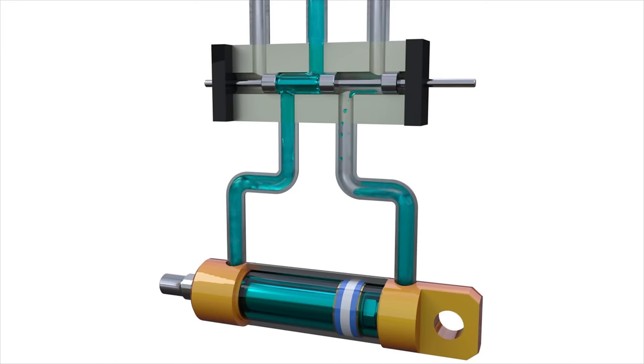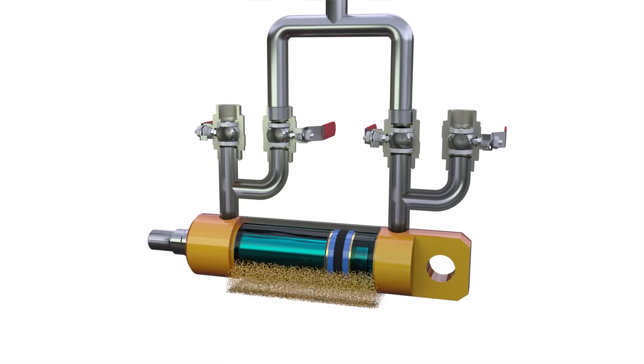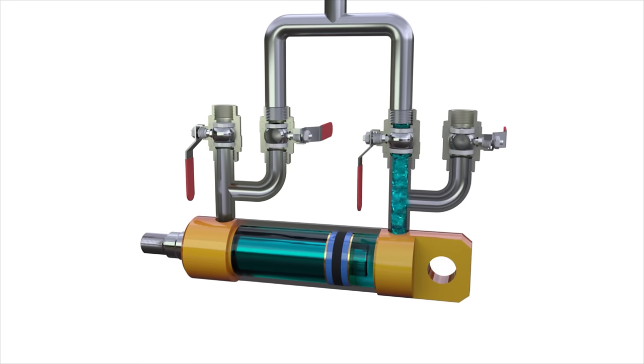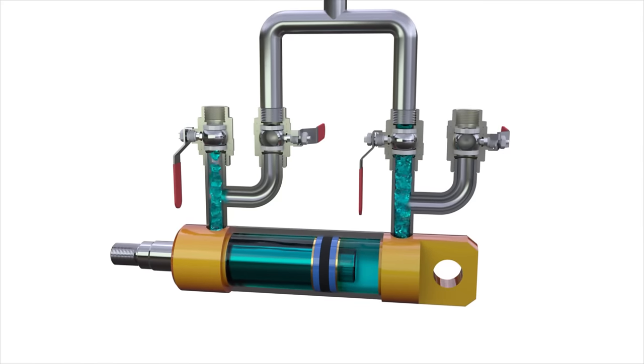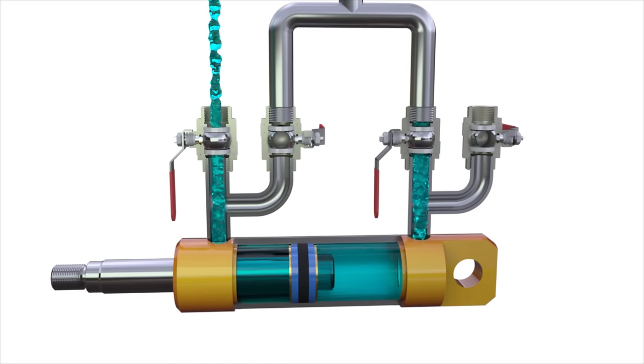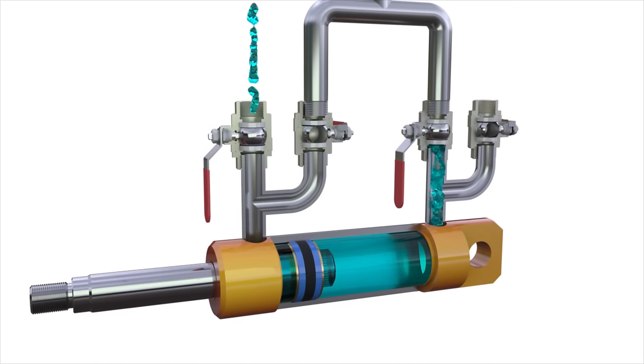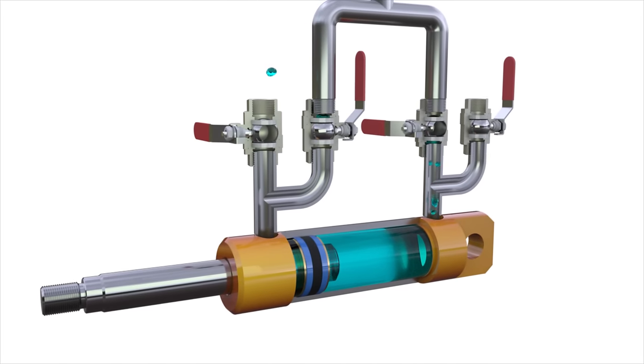You could do it by different ways. It's quite inconvenient to attach the pipe to the desired channel every time, but it's possible to use valves. Let's install two ball valves to attach the piston cavity with a pump or with a tank. Also, let's attach two similar valves to the piston cavity. By switching the valves, you can make the cylinder rod either move forward or back.